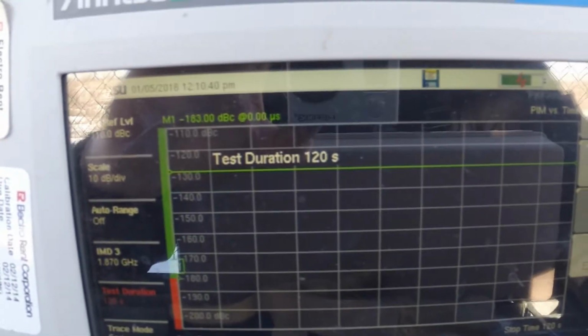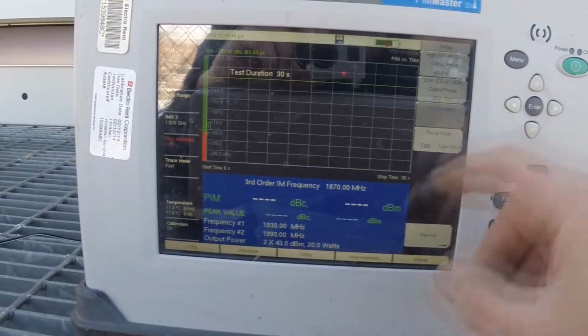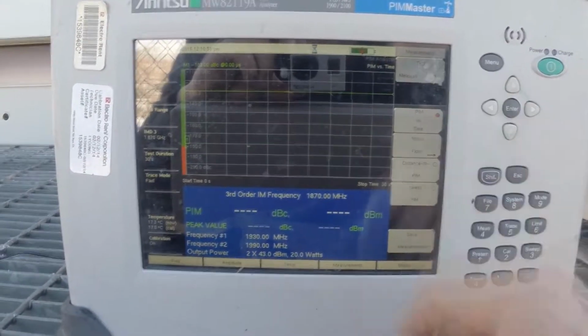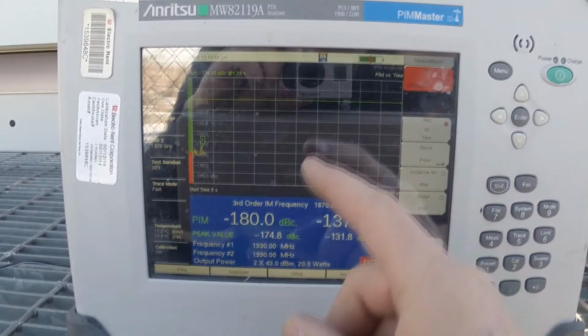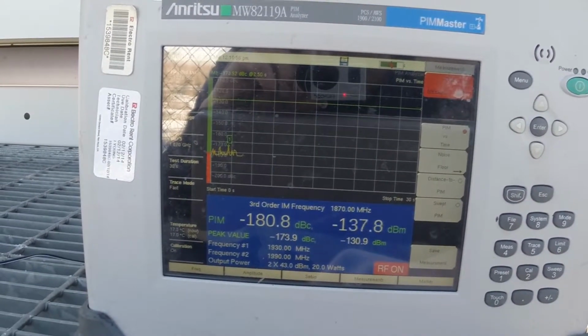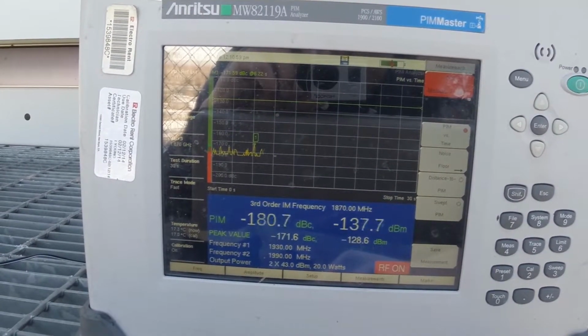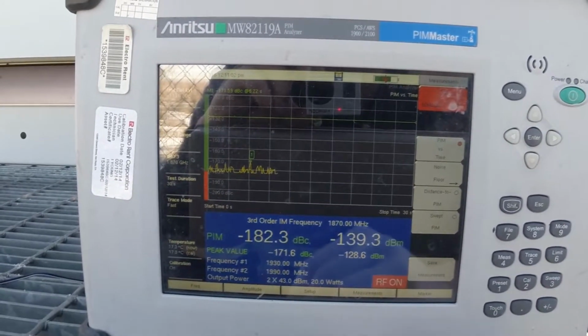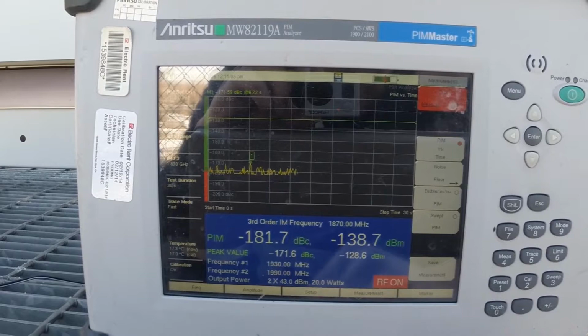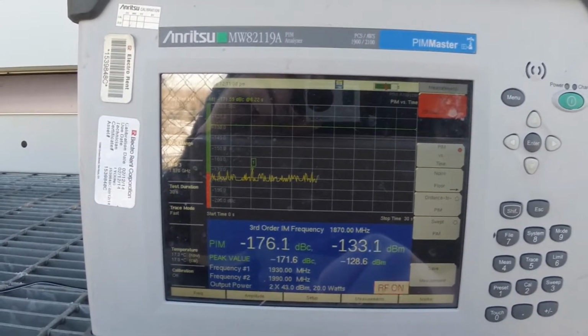To change our time, we can go to test duration. It'll pull up over here our test duration. Same thing with the sweep gear. As the sweep gear, we'll select that. We'll have our test duration up here. We'll go change it to 30 seconds and then select enter. And now we're at 30 seconds. So when I run this measurement, go back to measurements, test on. We're set in dBc right now. So we're reading at a neg 175 dBc, which is very good, which is what we should be looking for when the unit is calibrated, is neg 80s, neg 70s. It's okay to bounce around a little bit like that.